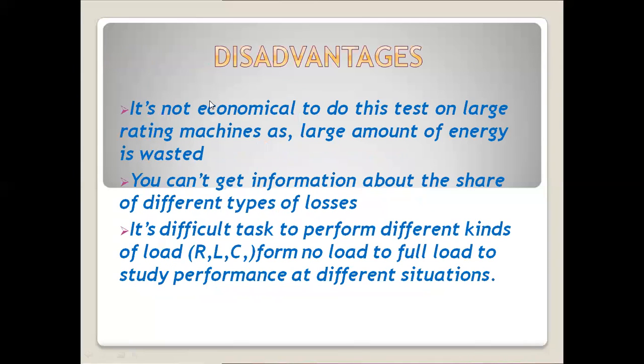The disadvantages are that it is not economical to do this test on a large rating machine as a large amount of energy is wasted. We can't get information about the share of different types of losses because we can only know the core losses or the iron losses, but we do not know about the hysteresis and the eddy current losses. And it is difficult to perform tests with different kinds of load, that is RLC, from no load to full load, to study the performance in different situations.